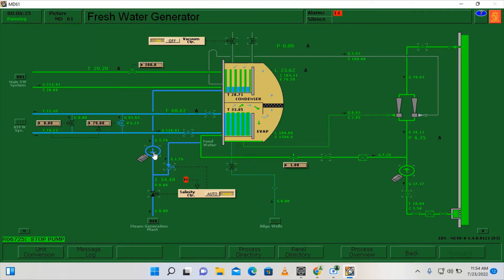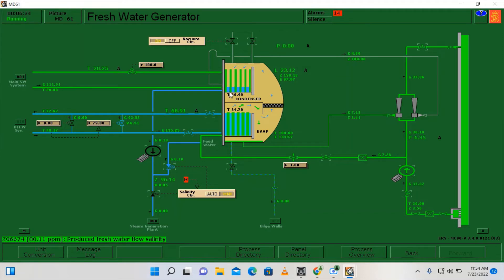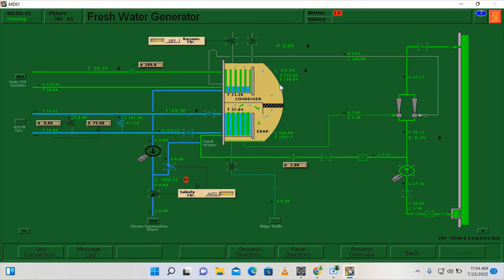I need to switch off the distillate pump. What happened here is that we have a high salinity, which means that our distillate water coming from our condenser is slightly salty. So what we are going to do now is turn off our fresh water generator and put it on standby and then rectify the leakage of our condenser plates.